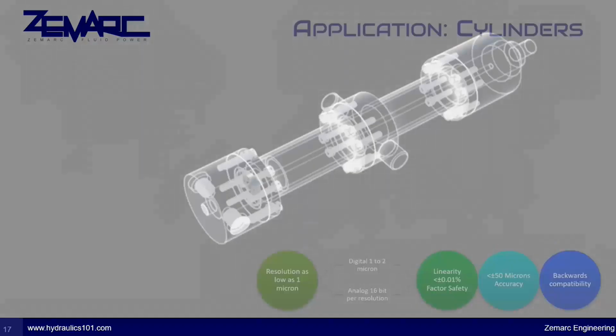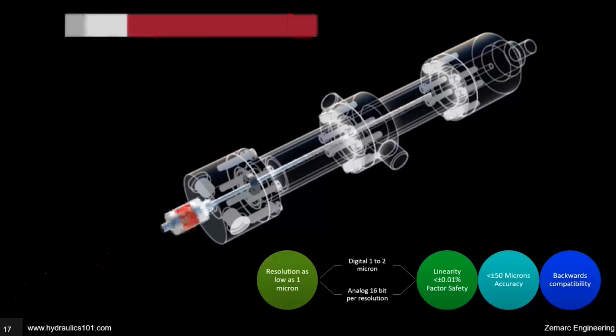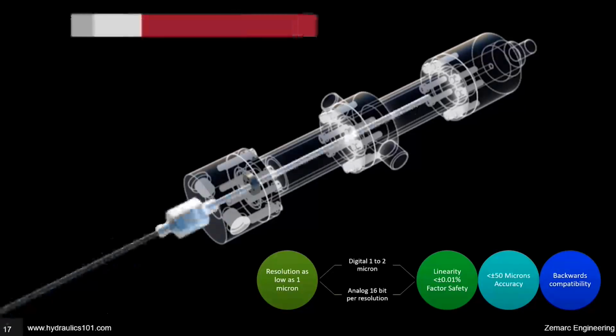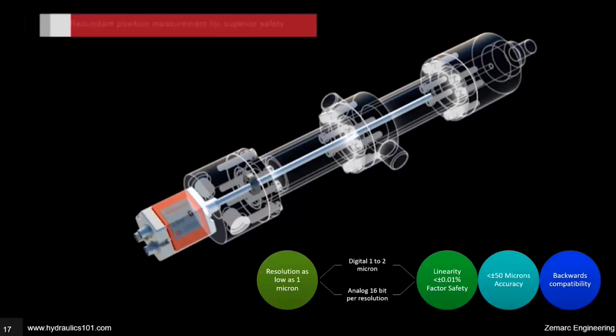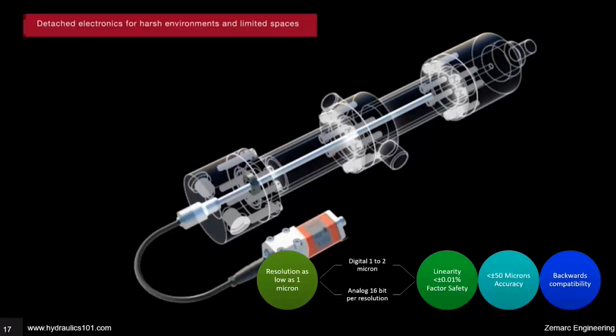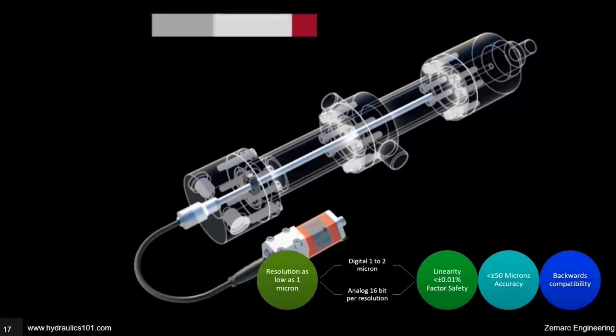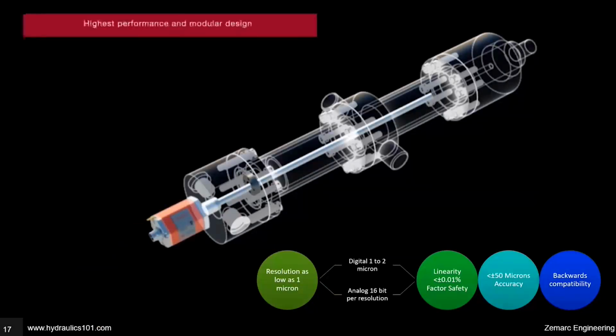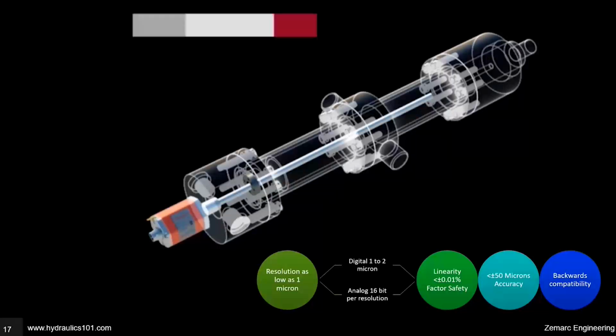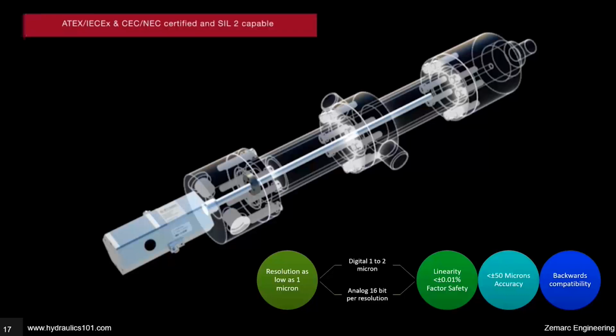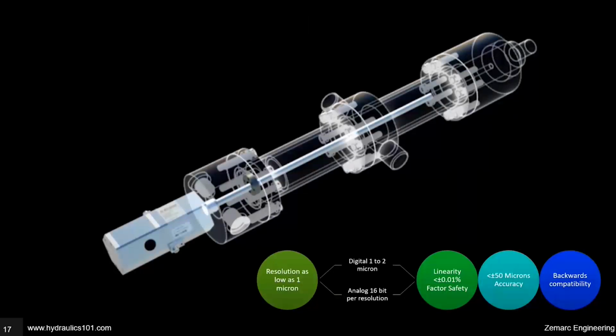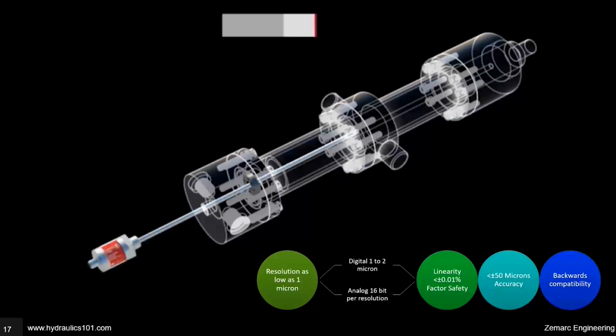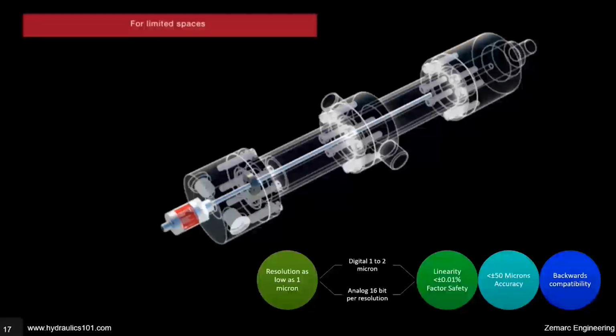A linear position sensor, like the Temposonics G and R-Series V, has very high accuracy and repeatability, conveniently requires no recalibration or ongoing maintenance, and offers very reliable, robust performance in harsh conditions. Specifically with R-Series V, we'll go over some exact details. It offers a digital resolution as low as 1 micron, and 16-bit resolution for analog feedback. Linearity is better than plus or minus 0.01% of full stroke, with less than plus or minus 50 microns of accuracy, and once again, backward compatibility with systems using previous generations of sensors, which is very convenient for upgrading and updating a system.